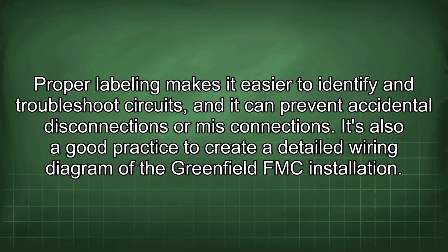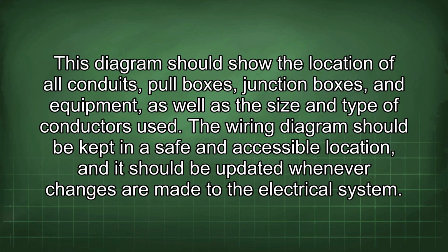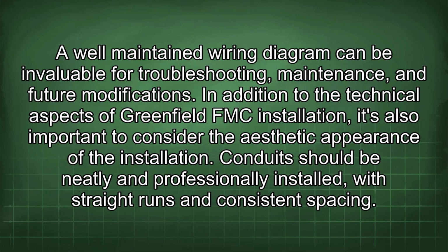It's also a good practice to create a detailed wiring diagram of the Greenfield FMC installation. This diagram should show the location of all conduits, pull boxes, junction boxes, and equipment, as well as the size and type of conductors used. The wiring diagram should be kept in a safe and accessible location, and it should be updated whenever changes are made to the electrical system. A well-maintained wiring diagram can be invaluable for troubleshooting, maintenance, and future modifications.